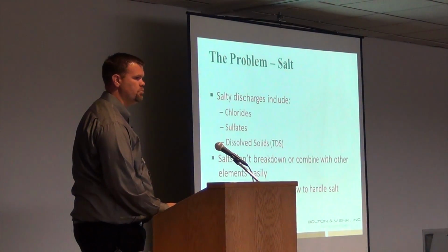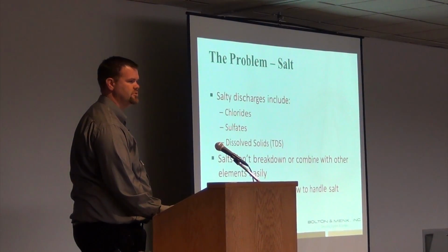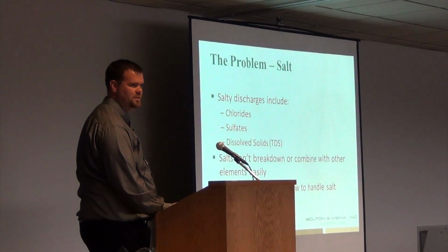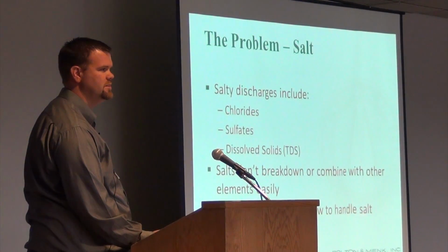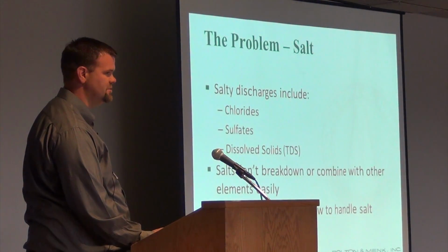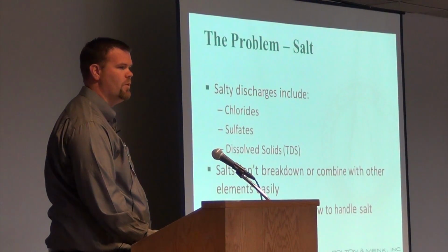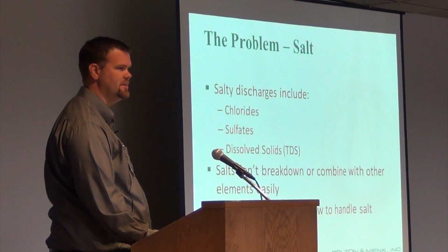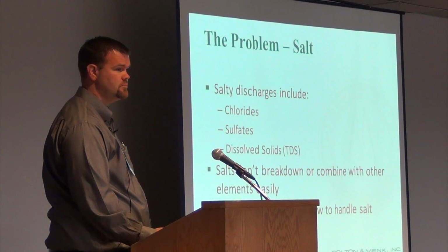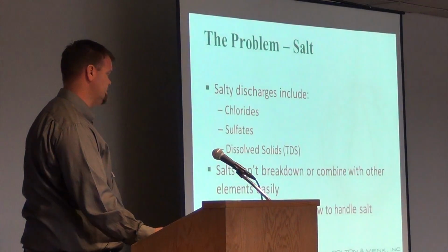The catch with these is they really don't break down. If you're thinking about a lot of the things in your wastewater stream, phosphorus or nitrogen or BOD, these are things that you use biological treatments to take care of, but those biological treatments won't deal with the salts. The salts are minerals that are in there, and they really don't go away with anything you can do. You just need to either keep them out of the waste stream, and that's what I'm going to concentrate on today, or concentrate them or separate them and take them to a different spot than the receiving stream.